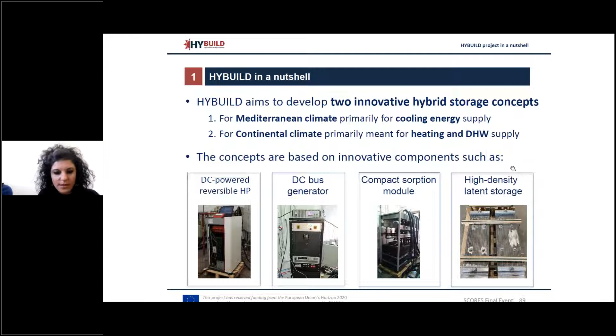It focuses on a vapor compression heat pump connected on the evaporator side to a low temperature latent storage, consisting of a three fluid heat exchanger where the refrigerant, the heat pump, the PCM, and the transfer fluid for the distribution system coexist. On the condenser side, it is connected to a sorption storage that allows better operation of the heat pump by lowering the condensation temperature. In addition, electrical energy is stored using high density, long life lithium titanate oxide batteries.